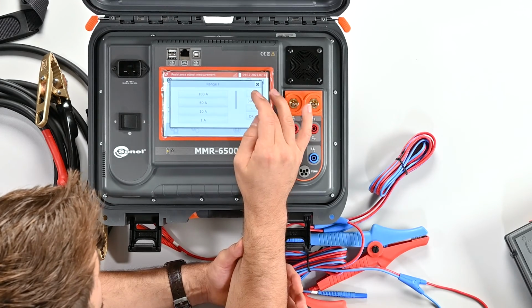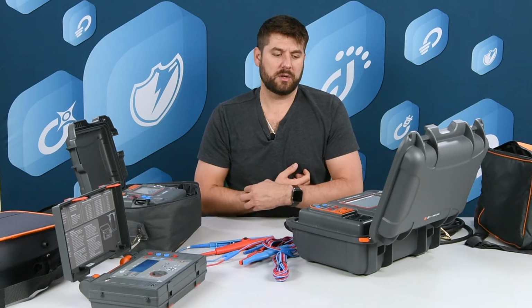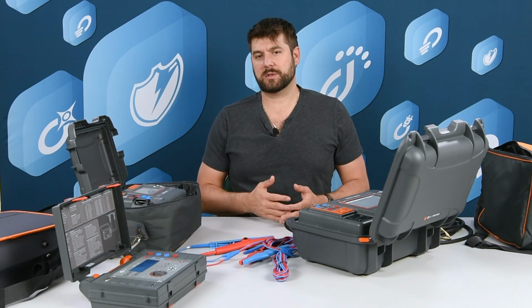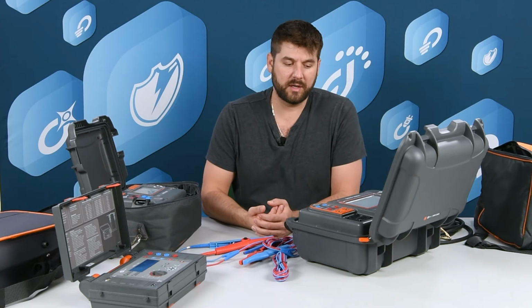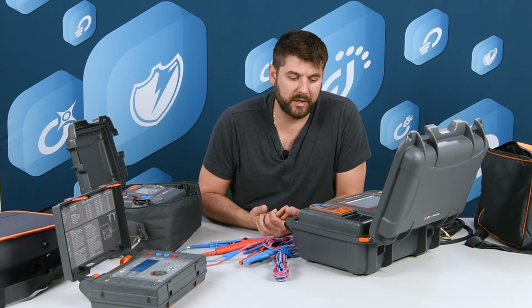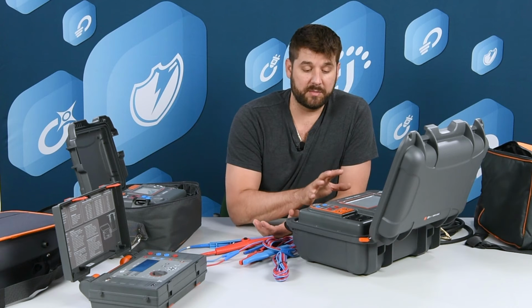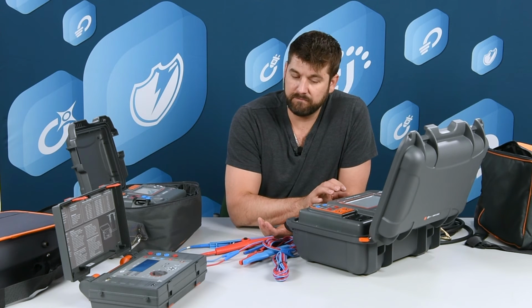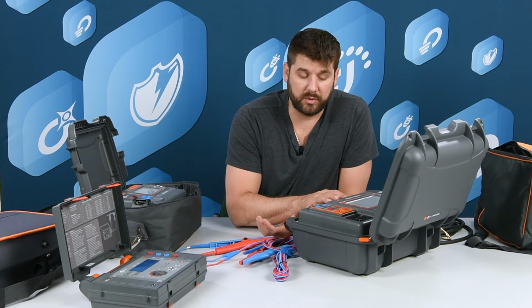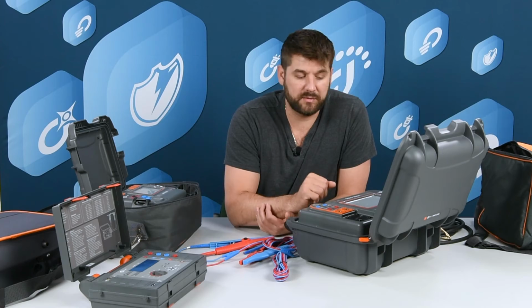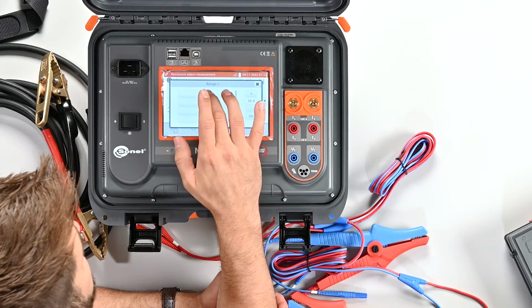Generally, it's a good idea to use more current if possible, up to what is close to where the device is rated. So if I have a breaker rated for 200 amps and I can get 200 amps out of this test set, push 200 amps through it, or whatever the specification is. So anyway, you select your test current.